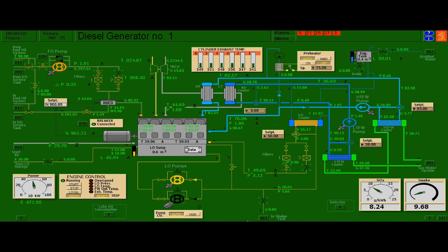Using this Kongsberg engine room simulator, we will do the following. Number one: confirm that the rotational speed of the eight-pole diesel generator is around 900 RPM and generates voltage with 60 hertz frequency based on the table in the previous slide. Number two: we will confirm that the frequency and RPM of an AC generator have a direct relationship, meaning increasing the RPM through the governor increases the frequency of the generated voltage, and at the same time, if we decrease the RPM, this should result in a decrease in frequency.